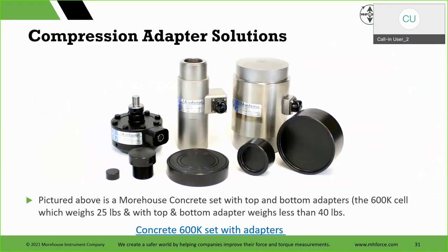And then we have kits. People say, hey, I go out and I do concrete machines. Well, if you're not using a top adapter on your load cell to calibrate those testing machines, there's a problem. So you should marry the top and bottom adapters. We have a whole compression solution. This 600K cell weighs 25 pounds. The whole kit, top and bottom, ISO compliant, everything's good there.